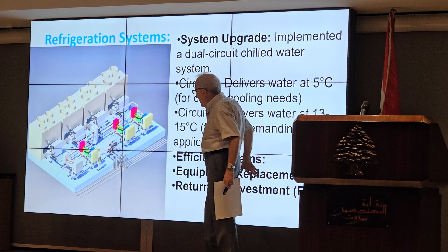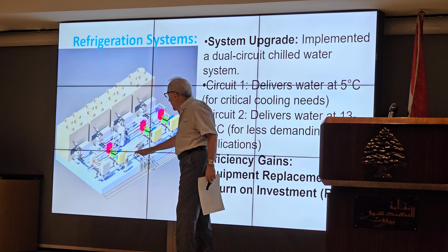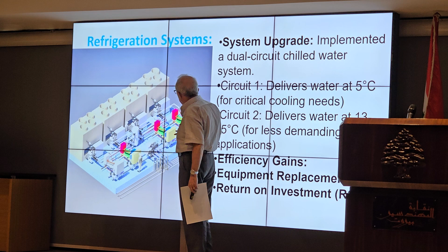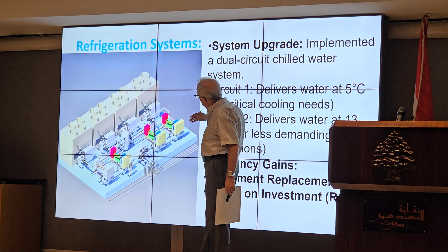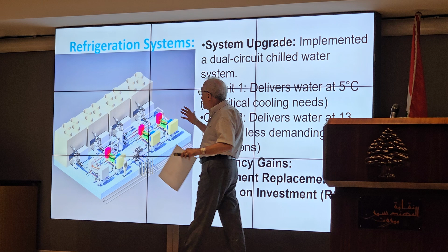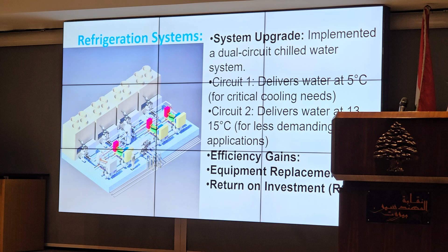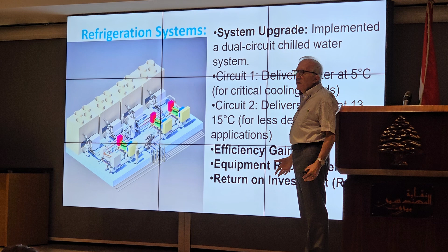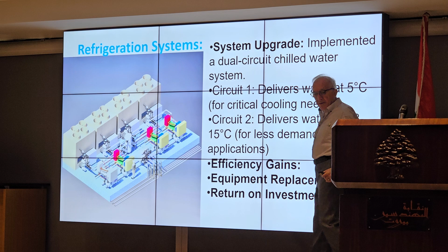This is a project that we have done also following the idea in the previous slide, that we have four circuits, but in fact 2 circuits. One that delivers at 5 degrees for the machine that needs 5, and one that delivers water at 15, 17 for the mold that they don't need less than that. And you imagine what is the economy, instead of having one chiller system, even if it is a chiller with ammonia that has a good COP in general, but it will not be 3 times or 4 times the COP of any other system.